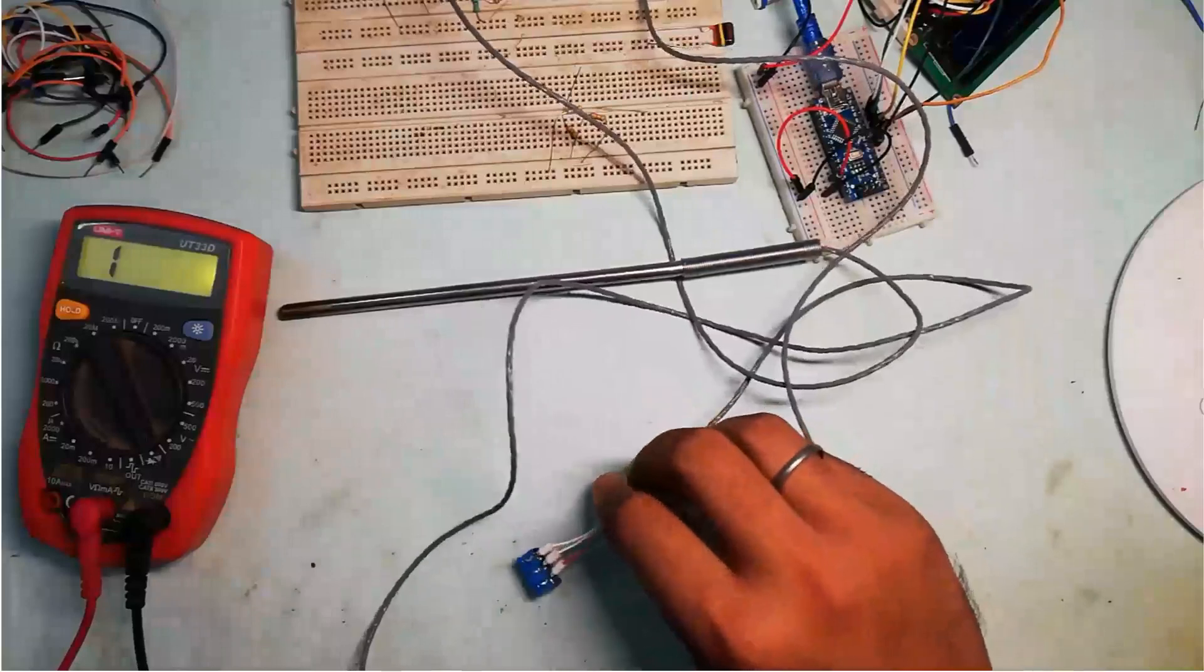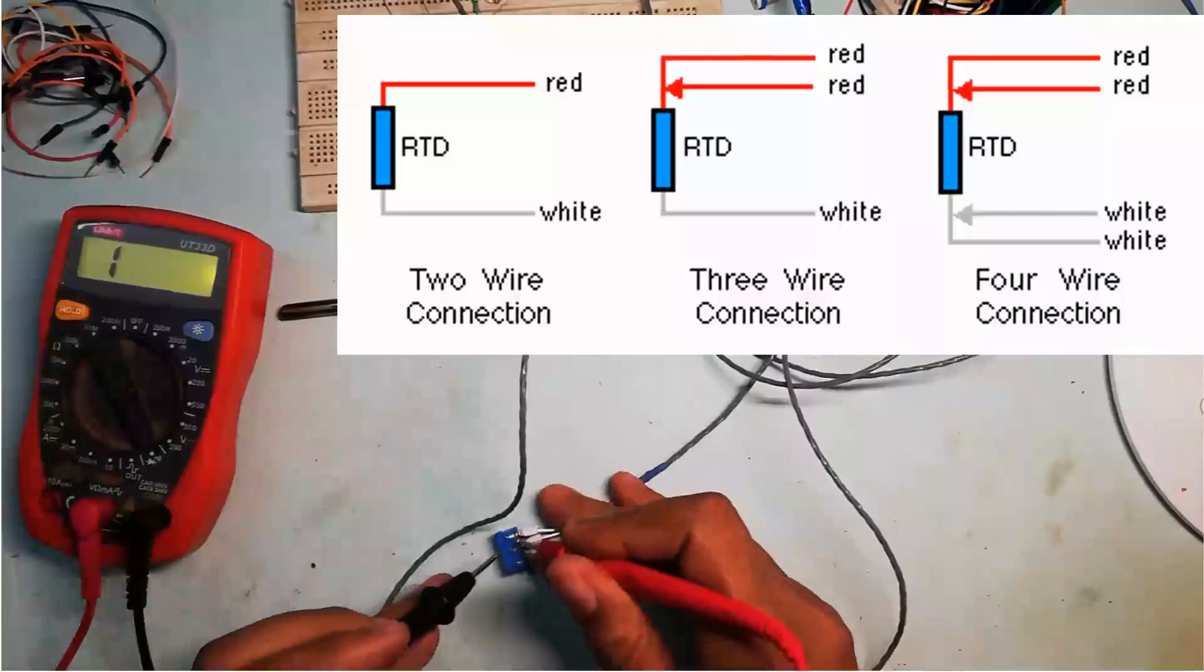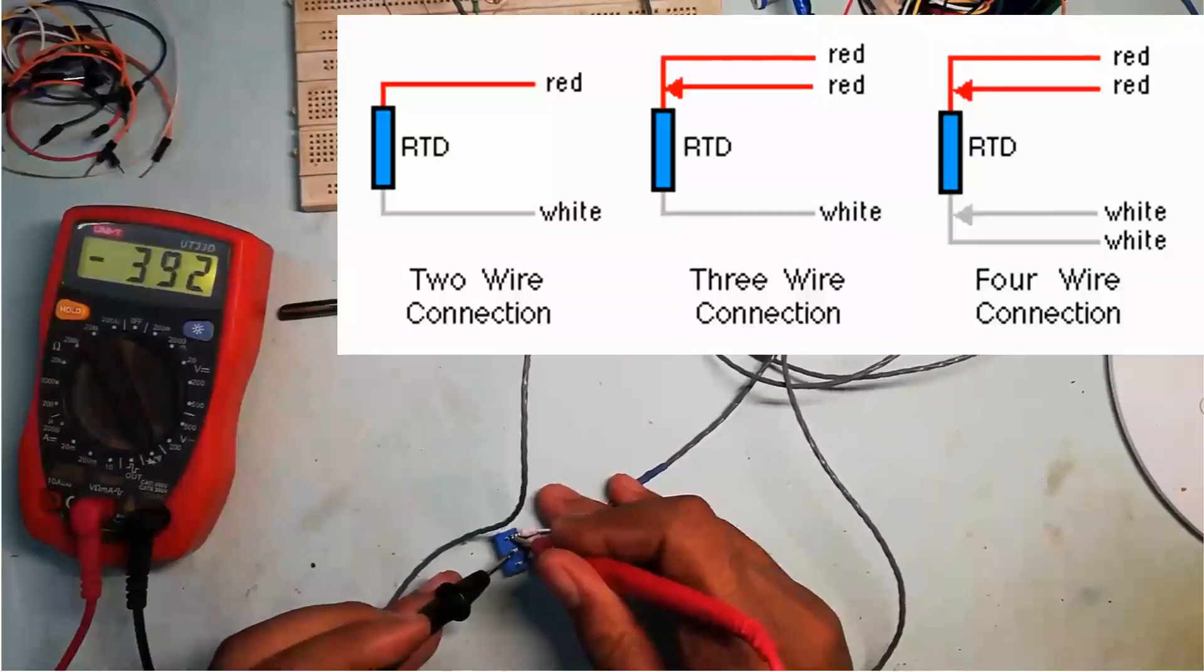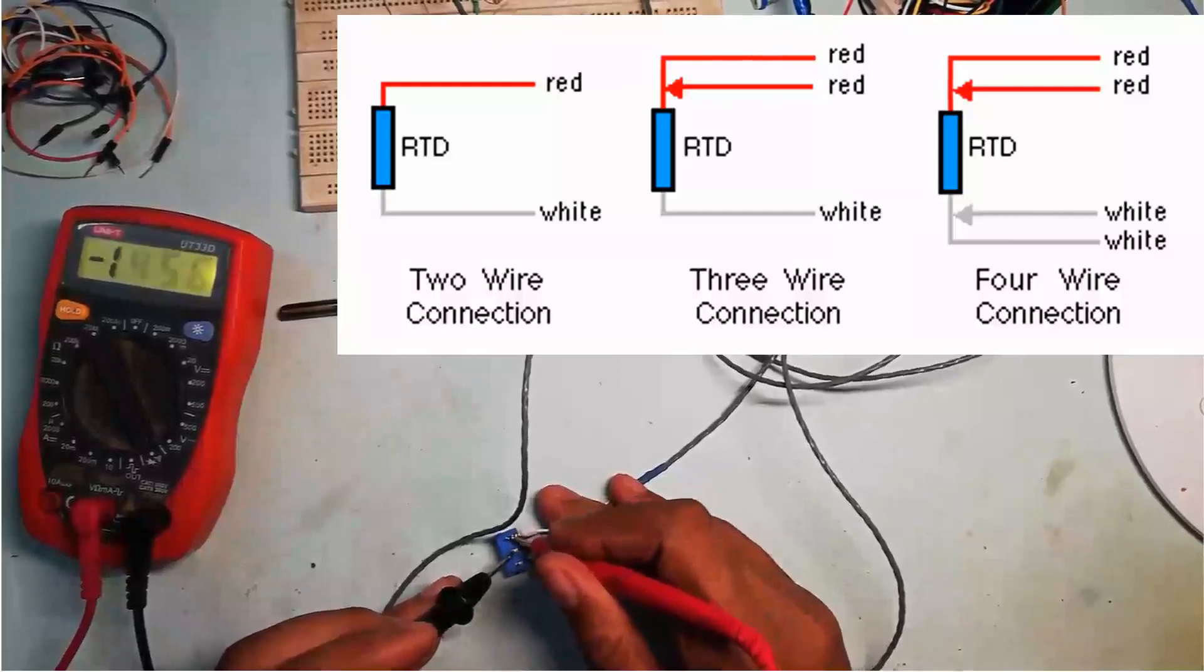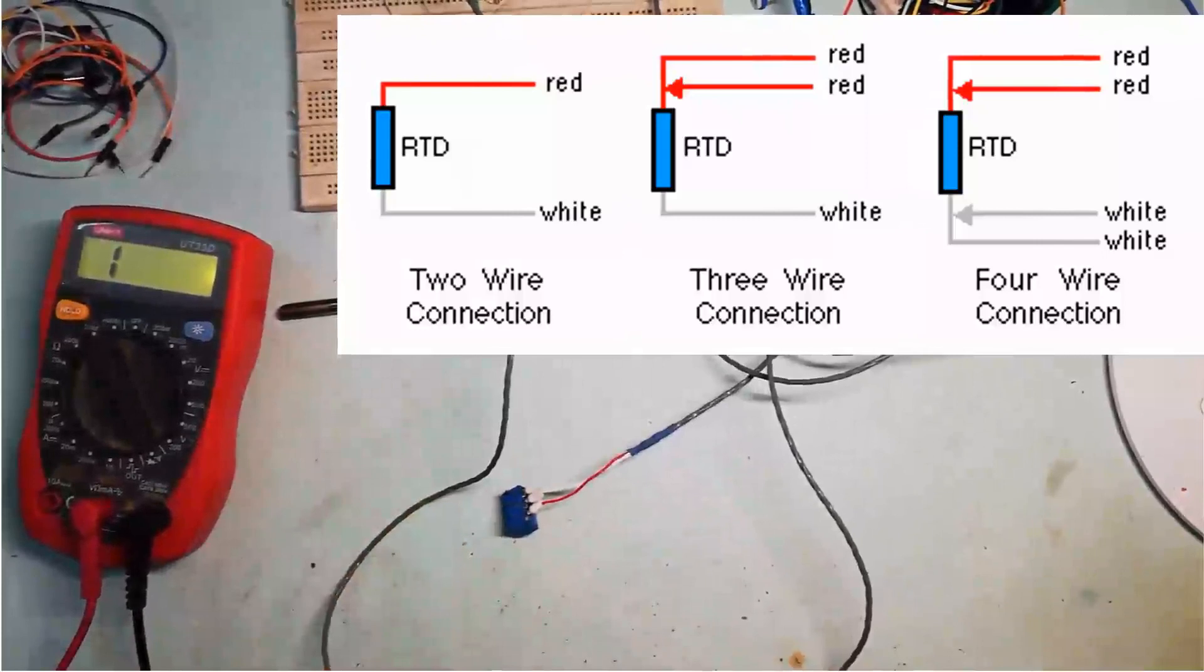Here I am going to interface a three terminal RTD sensor. For that, I am going to test the continuity. Adjust the multimeter in continuity test mode and check which two wires are shorted. As you can see here, these two wires are connected together. So if you have four wire RTD then two are for input and two are for output. They are shorted together.